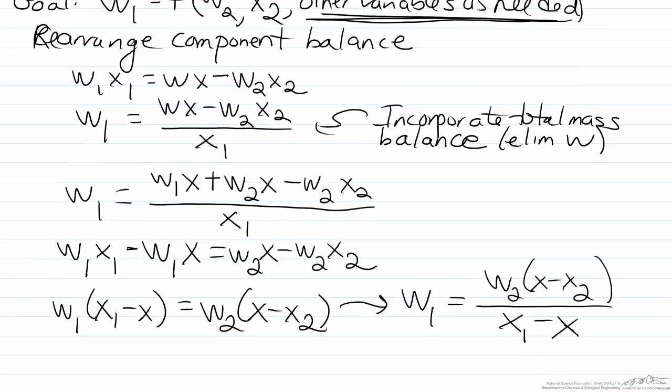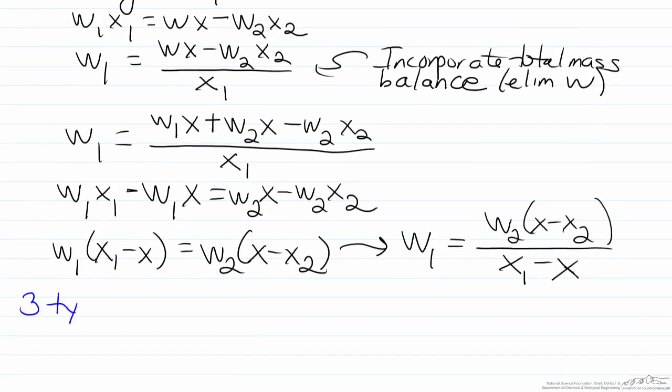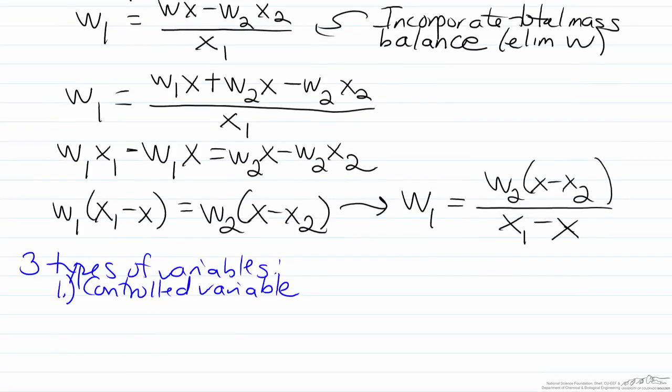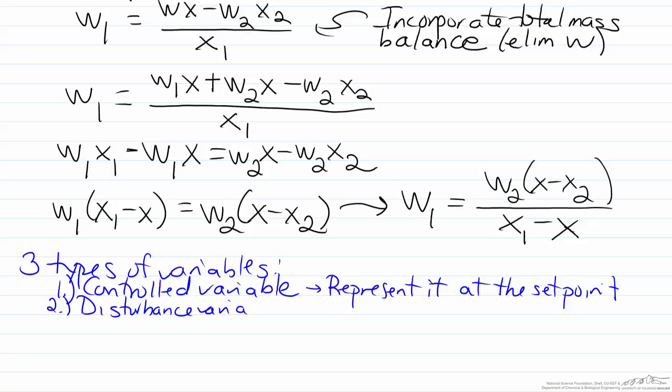When developing these static feedforward controls, we have three types of variables. The first is the controlled variable, and remember we don't have the measurement of this controlled variable, so therefore we will represent it at the set point. The second is the disturbance variable or variables. Here we will just leave them as is, because they are variables which we are measuring using the transmitters.